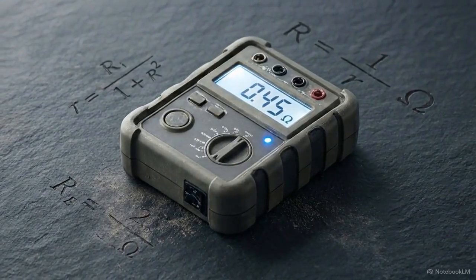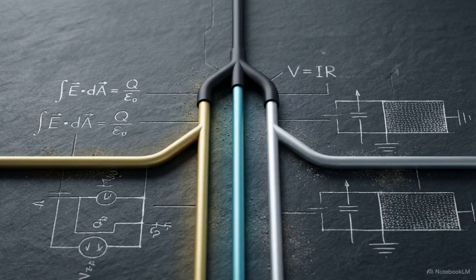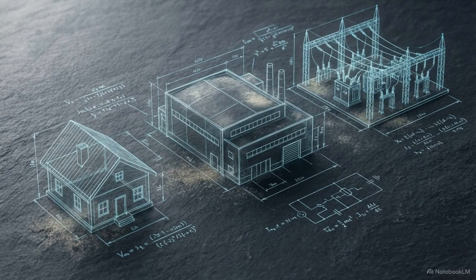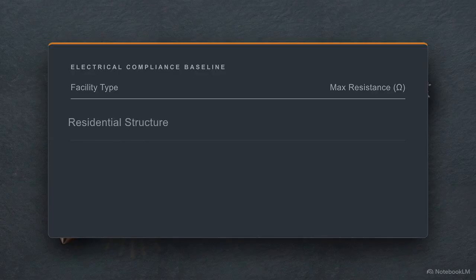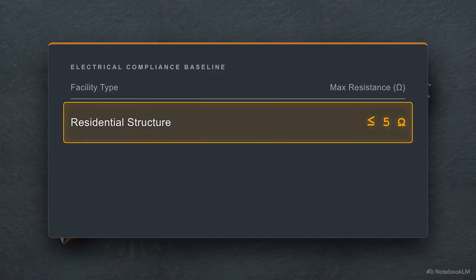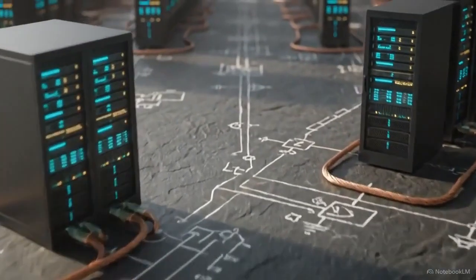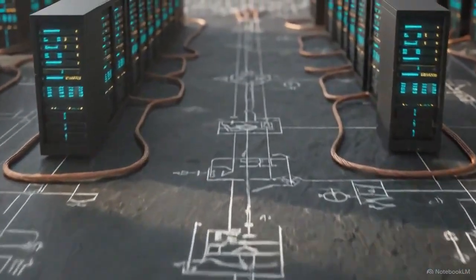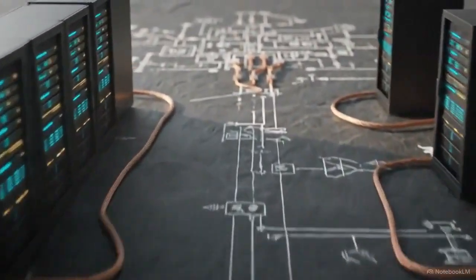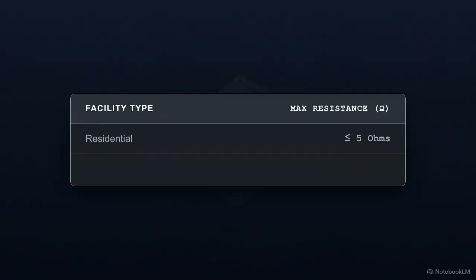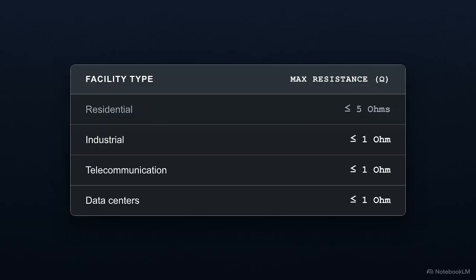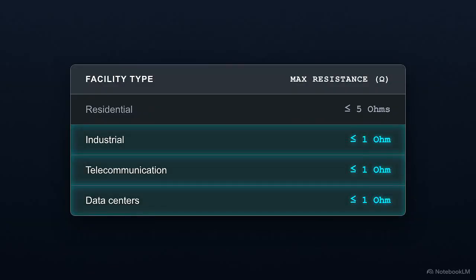The acceptable resistance for an earthing pathway is not a single universal number. It is strictly dictated by the scale and function of the facility. This chart details the required limits. For standard residential structures, the earthing resistance must be maintained at or below 5 ohms. However, as an operation's reliance on continuous uptime and data integrity scales up, the tolerance for electrical resistance scales down. Industrial complexes, telecommunication hubs, and data centers process massive amounts of sensitive information. They require a much stricter grounding threshold of less than 1 ohm.